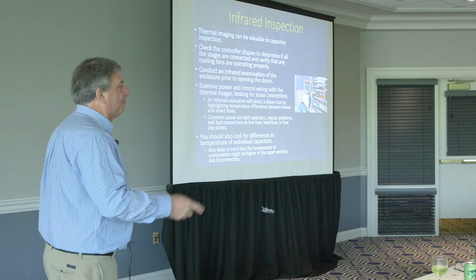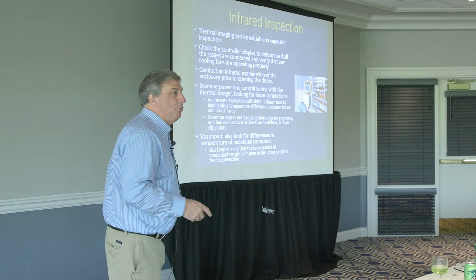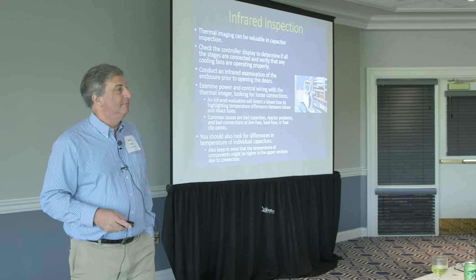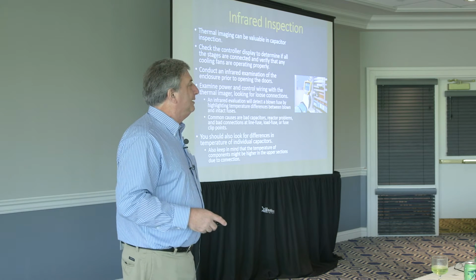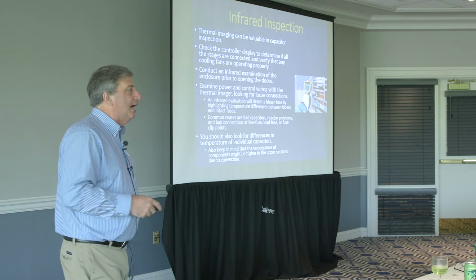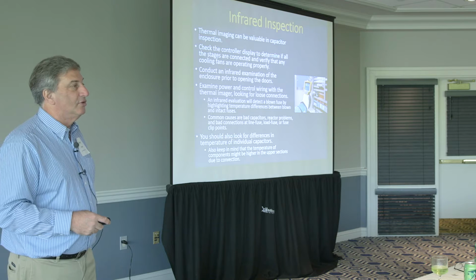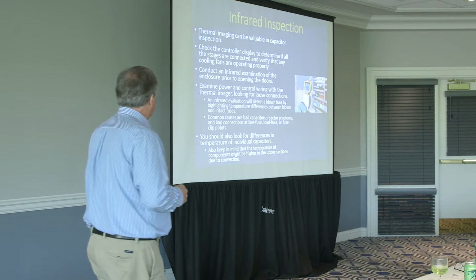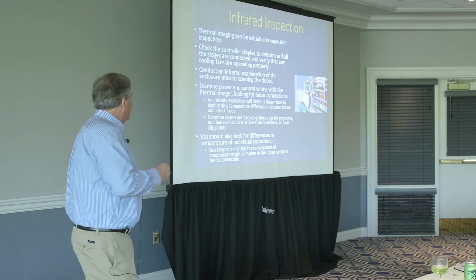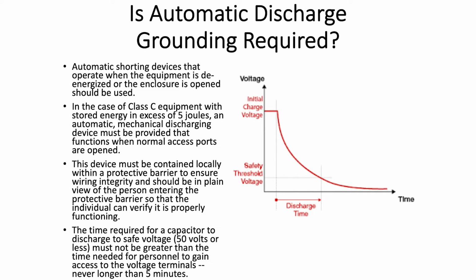So we went through the procedures. Did we really discharge all the caps? Or was there something we forgot and we got one or two sitting there that's not discharged? We can see that on an infrared heat gun. Okay? So some of those types of issues become important. Is automatic discharge grounding required? Okay? Well, maybe. Depends on the class of the capacitors and the joule size of energy that they store.